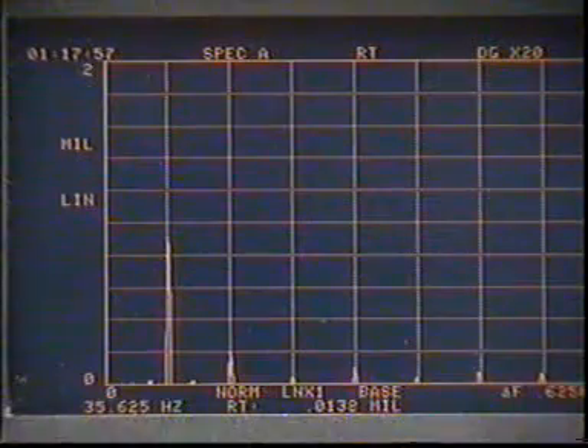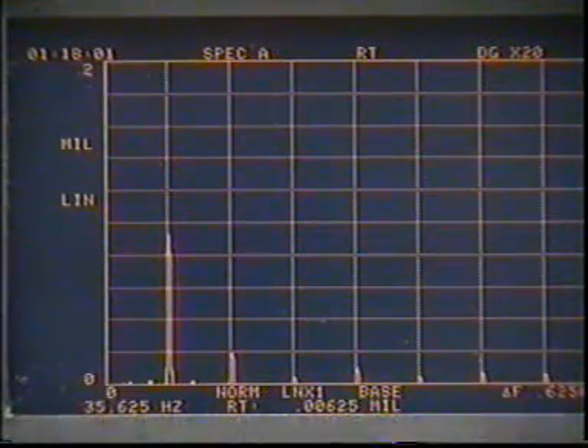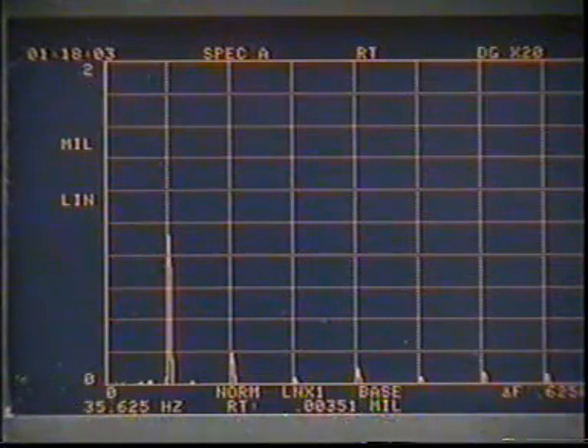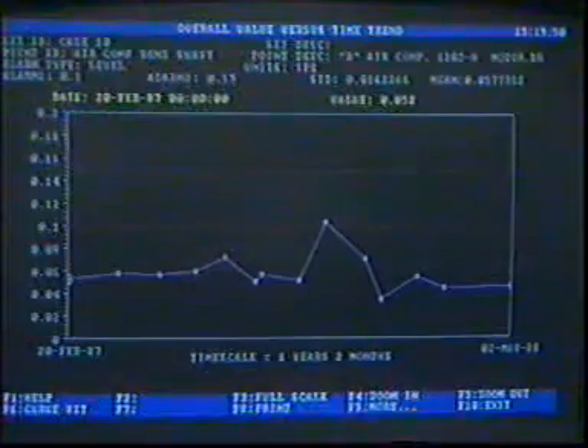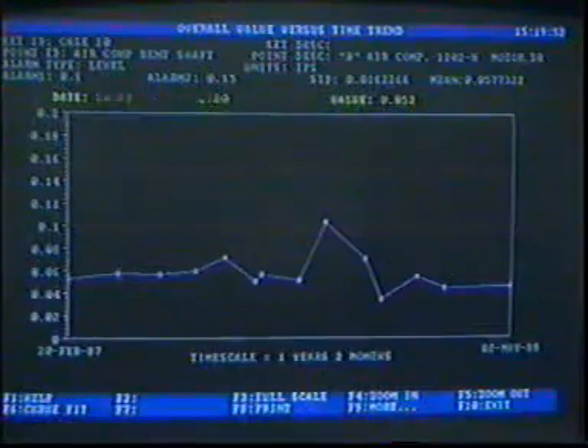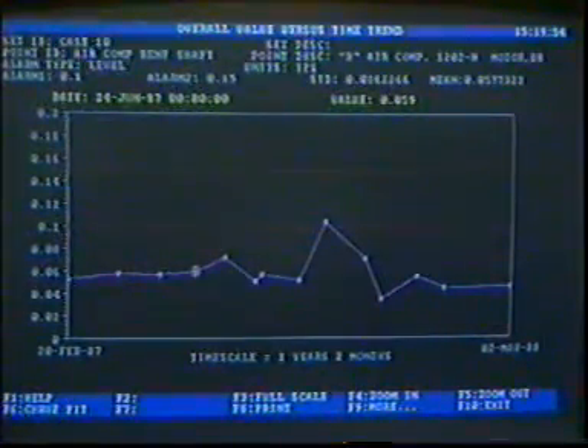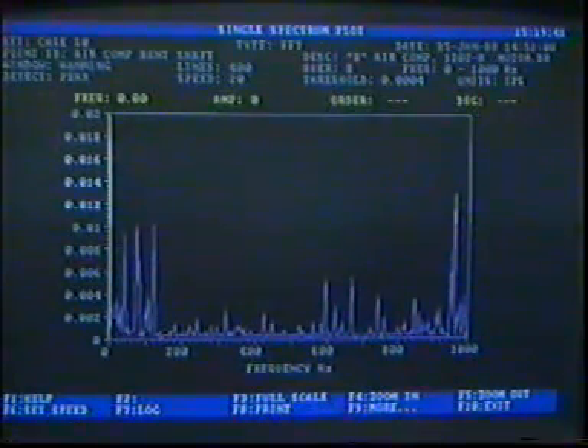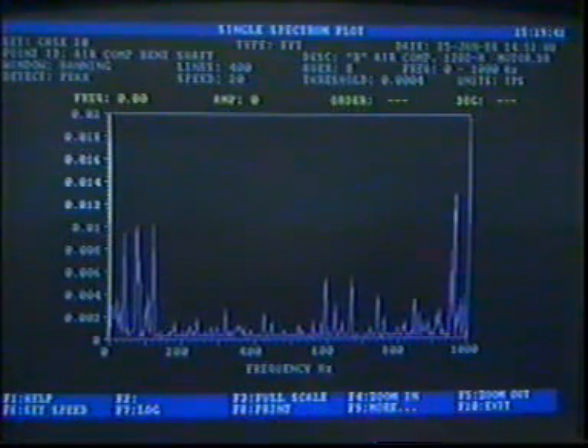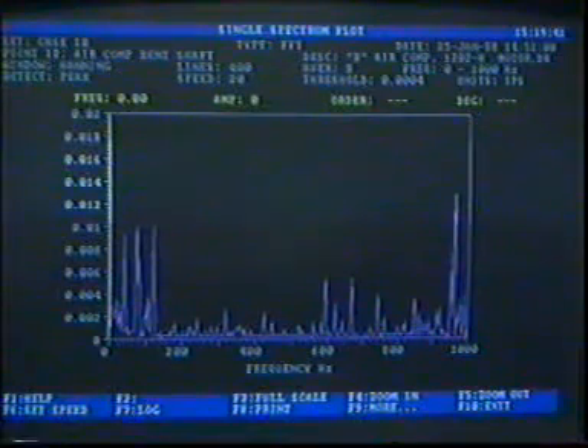Something that is impossible to do on a time domain or oscilloscope plot. Secondly, surveillance measurements are easy in frequency domain. The signal is assigned a value, and over time these values can be trended. Finally, small signals lost in the time domain are detected in the frequency domain. This means that small defects can be detected while they are still small.